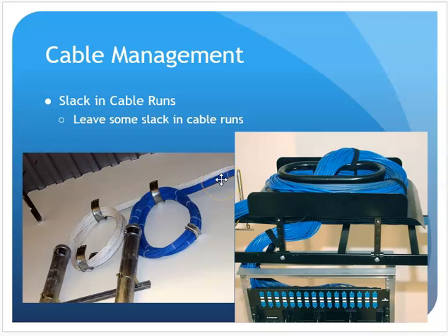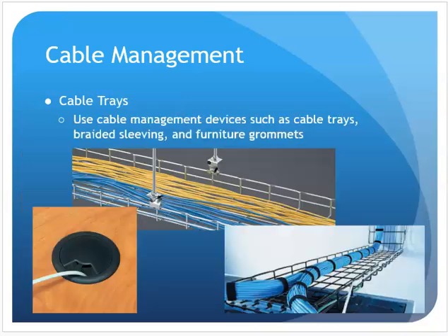As I'm routing my cable, I need to make sure I leave some slack. That way I have that to uncoil and move equipment racks around or potentially service equipment, then put it back. So I need to make what they call service loops. My cable trays should be supporting my cabling from closets out to work areas and so forth. I'm going to pick up here in the next podcast.